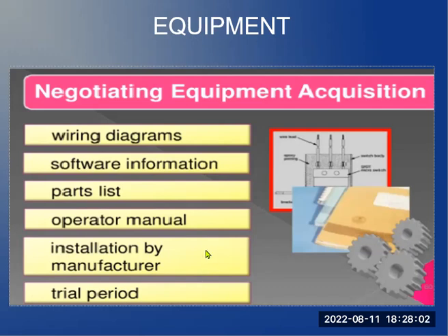So the software application is for testing the equipment. Next, there should be a trial period. It depends on the agreement between the lab and the manufacturer, on the length of that period. It's either 3 months or 6 months, just to test the functionality of the equipment and its reliability. During your trial period testing.